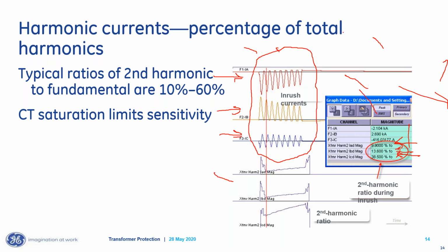And the reason it would be, I didn't mention this, but typically you would set the level of second harmonic at 20%, right? So the C phase is well above that 20%, but it's the only one that's above. So I'd trip this thing off if they did it per phase. The old electromechanical relays, they'd trip on this because they didn't really have a choice. They didn't even have a setting for the level of second harmonic. It was just hard set at 20%. And if I analyze the 2 out of 3, well, B and A phase are both less than 20%. So I wouldn't restrain there either. I'd misoperate when I try to energize the transformer.